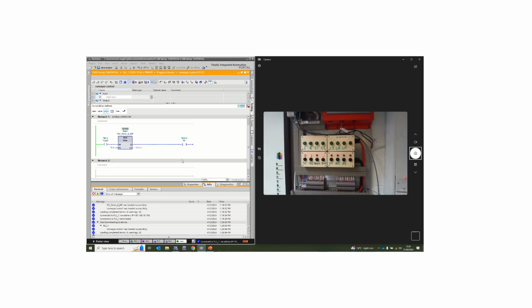So previously what I had is when an input came on, which is SWG, I got the output for 3 seconds amount of time, which is maybe what you want to achieve. The other timer here is a TON timer or an on delay timer. It will give you the output once the PT, or in our case 3 seconds, has actually occurred. So I need to press and hold my input SWG for 3 seconds amount of time before the output turns on. Now the difference is with this one, the output will stay on until you lose the input SWG. So I have to press the button again to lose that, and now it goes off.